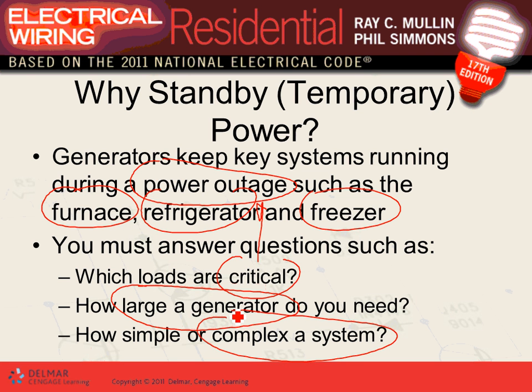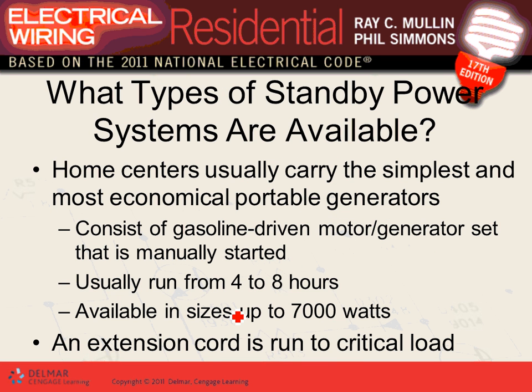If you're not starting your AC units, and if you don't have electric dryers and electric ranges and air conditioning, if you don't run these, a 7.5 kW generator should cover almost everything in your house, except the major loads. Okay, so a lot of people have a smaller generator to back up just the essential critical systems. What types of standby power systems are available? There are a couple of things, guys. You can go from a very simple system, most commonly portable generators, that's what a lot of people have.